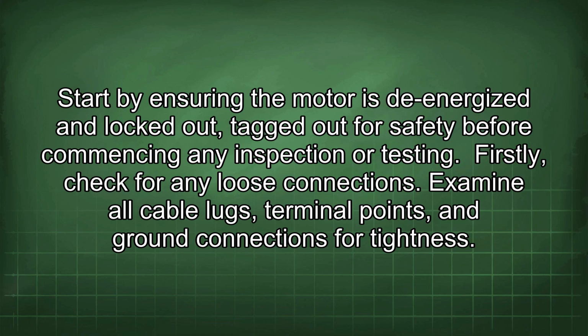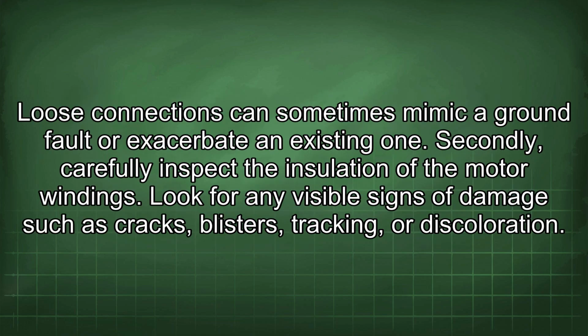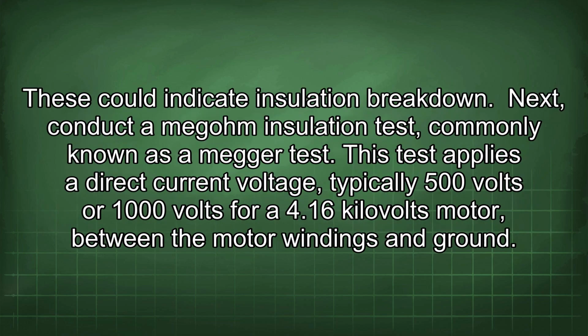testing. Firstly, check for any loose connections. Examine all cable lugs, terminal points, and ground connections for tightness. Loose connections can sometimes mimic a ground fault or exacerbate an existing one. Secondly, carefully inspect the insulation of the motor windings. Look for any visible signs of damage such as cracks, blisters, tracking, or discoloration. These could indicate insulation breakdown.